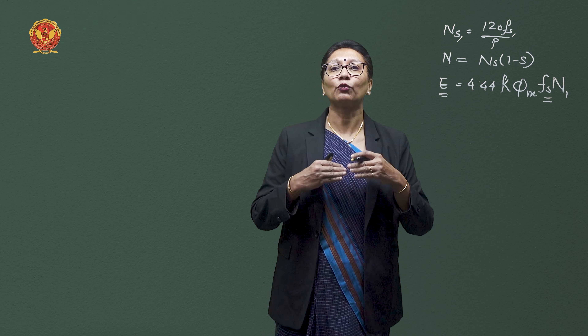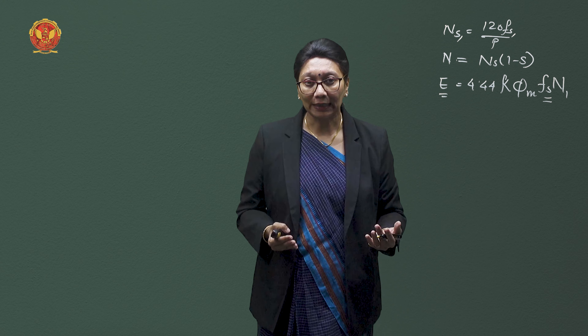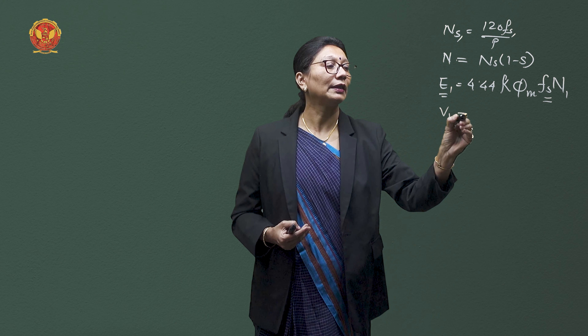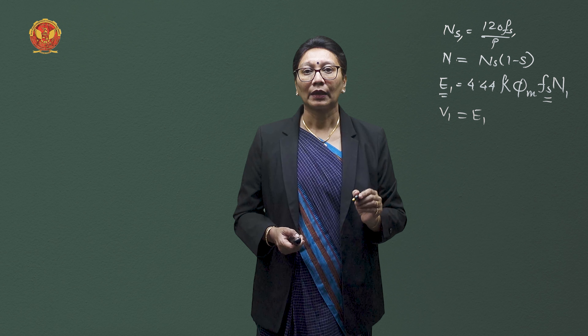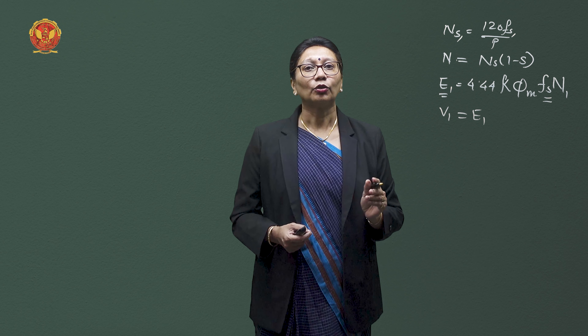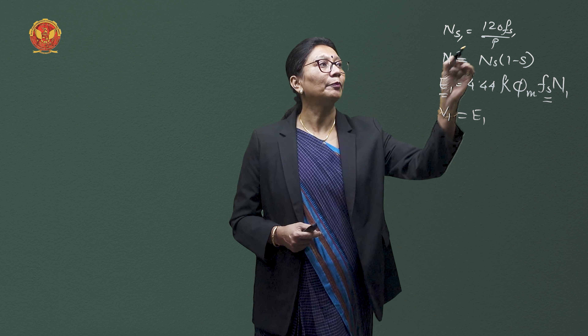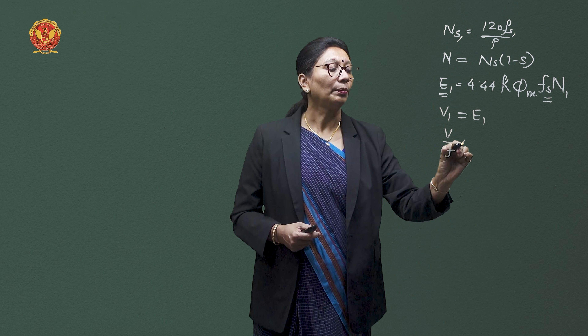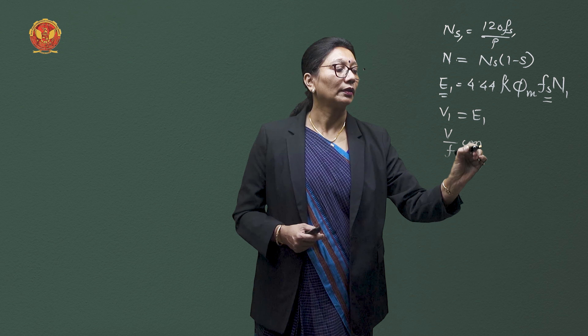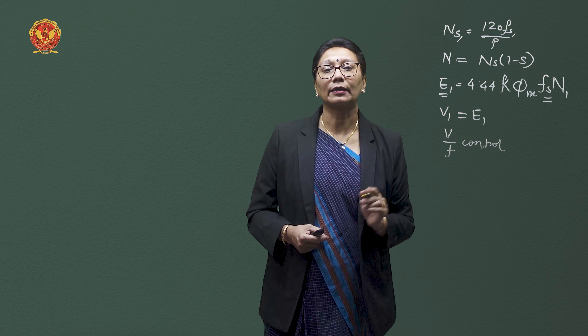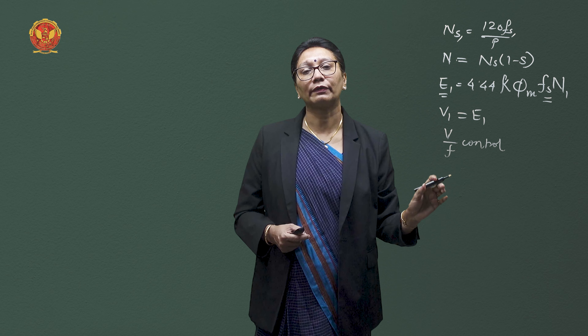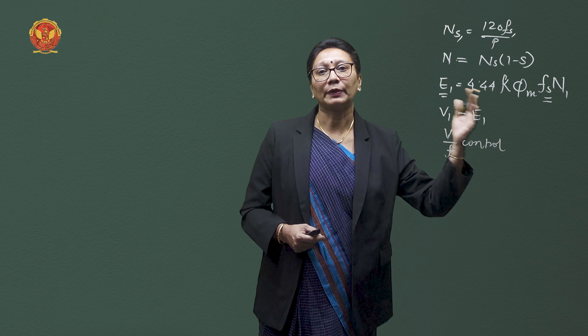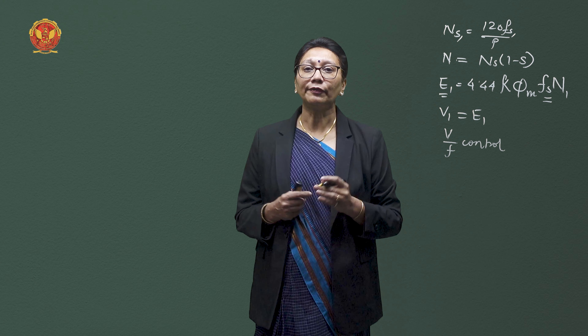If we neglect the stator voltage drop, then we can say V1 is approximately equal to E1. This way V by F control is possible, and we can understand that by varying stator voltage and frequency together, variation in speed can be achieved.